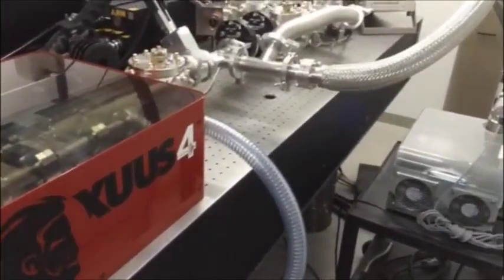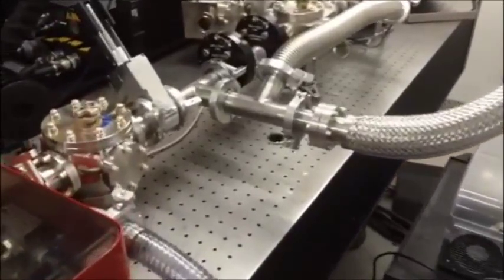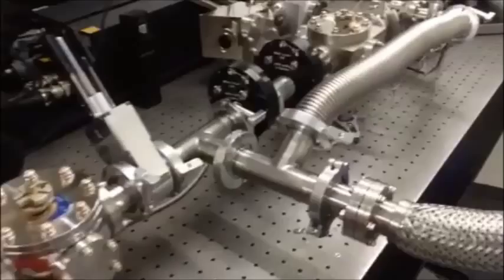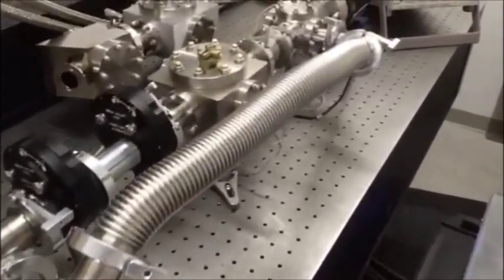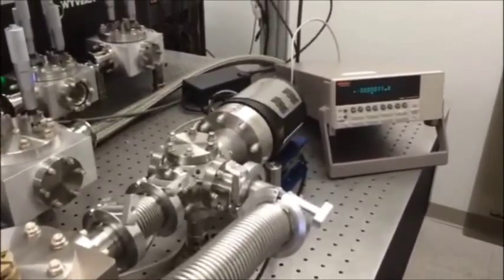The XUUS includes a vacuum beamline to deliver the desired EUV output to your experiment. Some components of the beamline remove residual IR light, while other components filter, focus, and detect the desired EUV output.